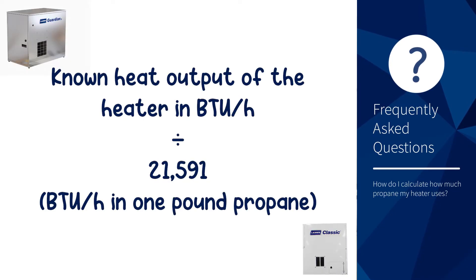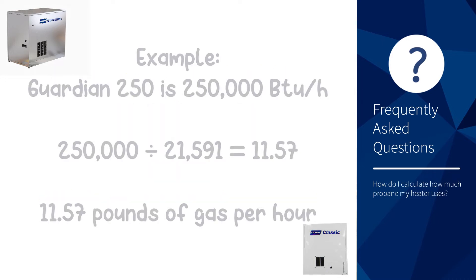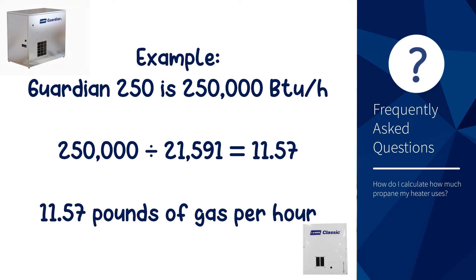Take the known heat output of the heater, expressed in BTU, and divide that by 21,591, which is the BTU in one pound of propane. For example, a Guardian 250 is 250,000 BTUs — divide that by 21,591 and you get 11.57 pounds of gas per hour.